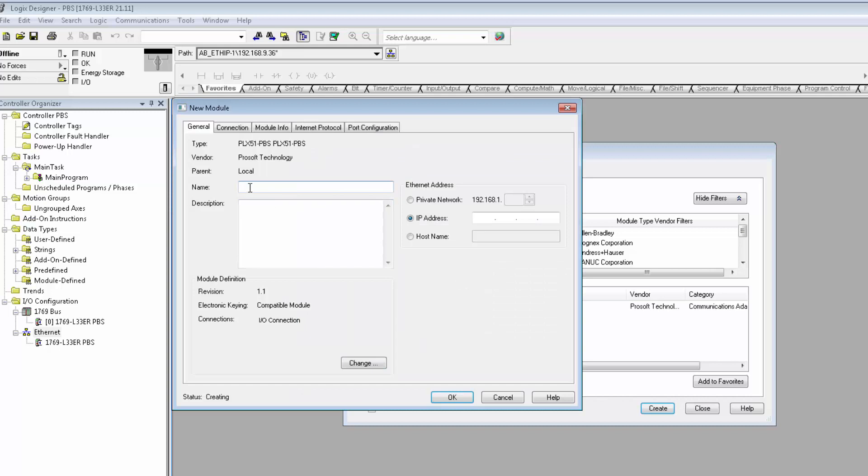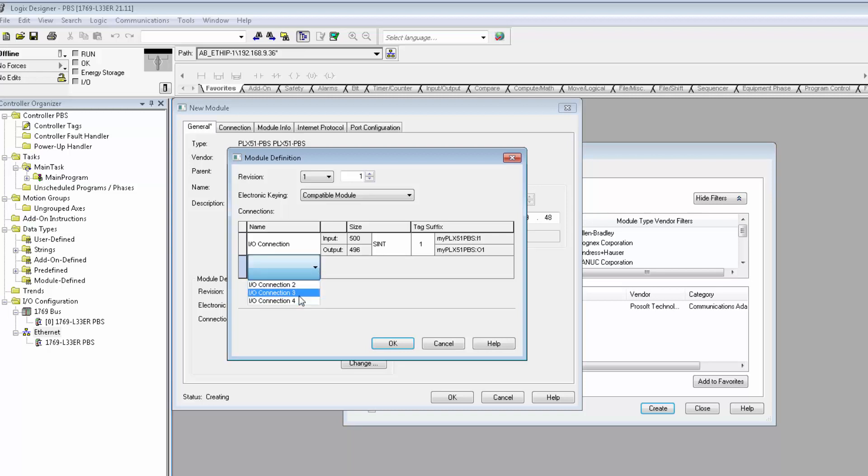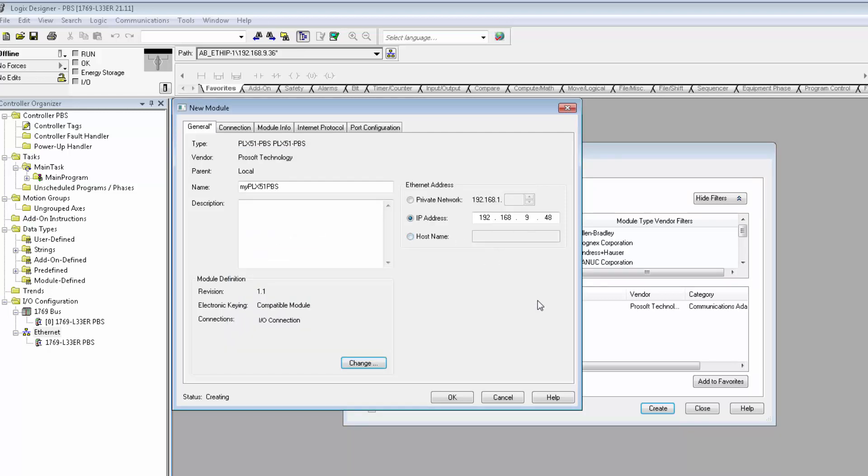This AOP will only work for Logix version 21 or higher, by the way. In the New Module window, give the module a name and enter the IP address that you assigned back in the configuration utility. We'll click Change under Module Definition, and here is where you set up the I.O. connections. Now I only have one connection for this training, so I don't have to do anything. But if you do have two or more, you'll need to be sure to add them in here. Now we'll bring in the ladder file that we exported.